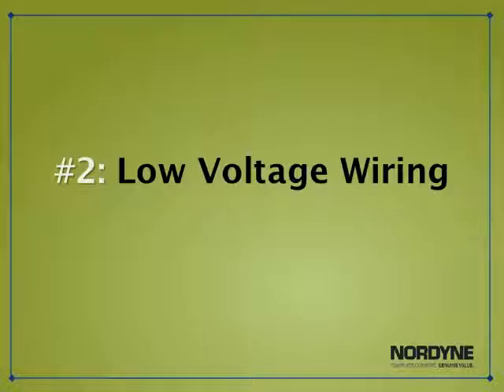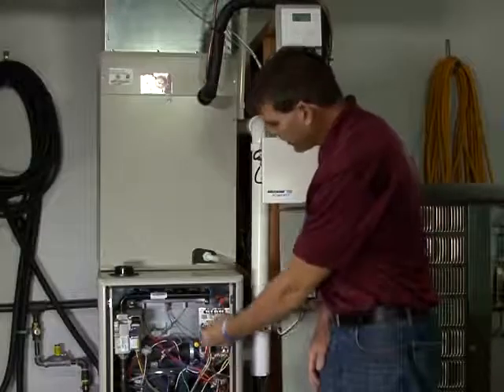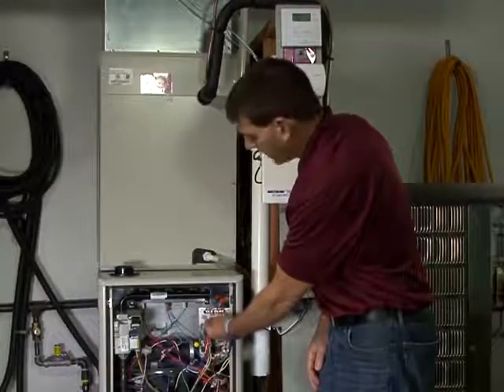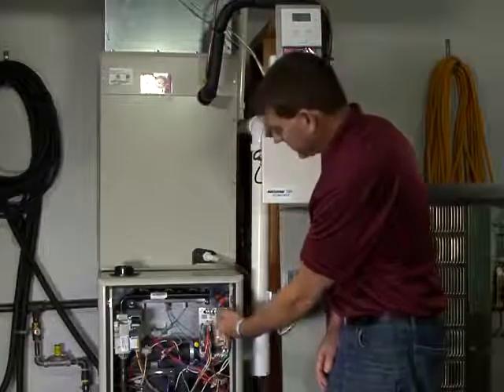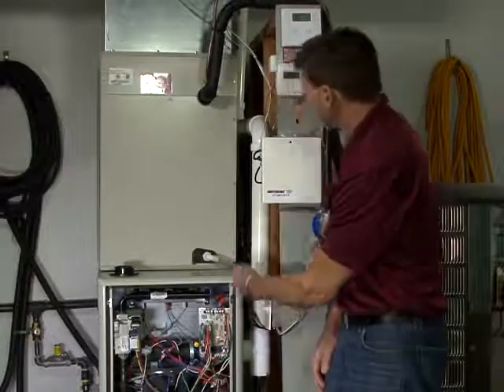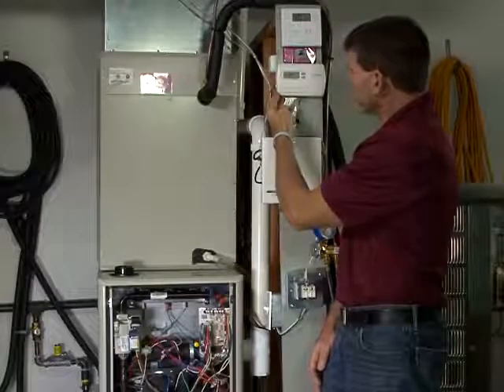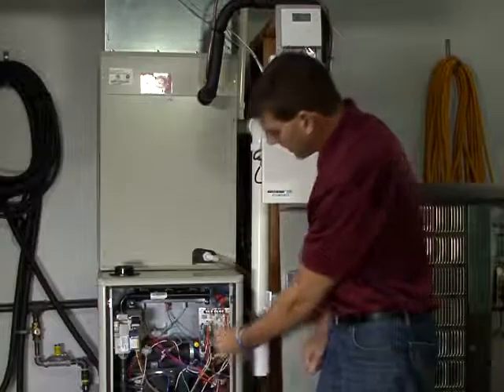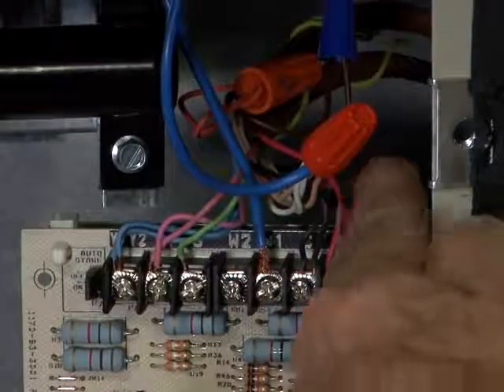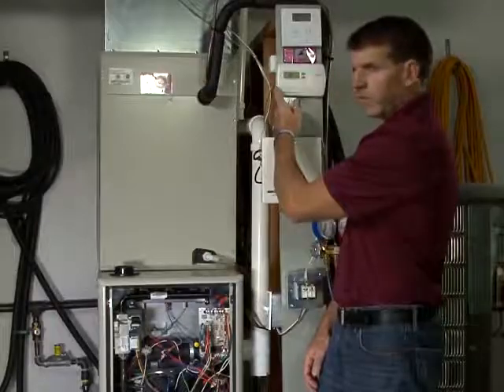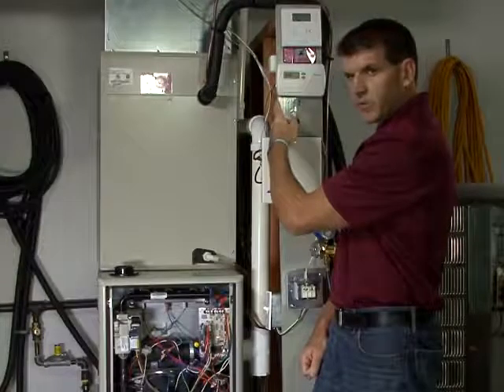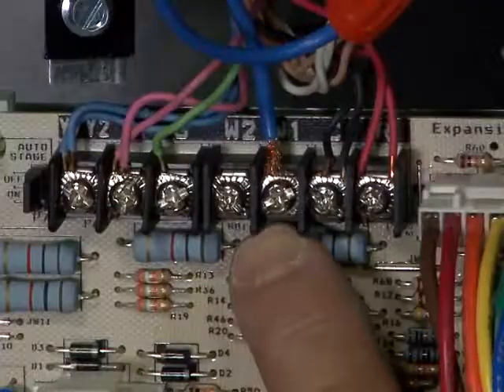Our next topic we're going to cover is a low voltage wiring circuit. Our low voltage wiring is what connects our thermostat to our interface control board. We also refer to this as our control wiring. Our control wiring connects at our interface control board on the terminal strip. It then runs through the thermostat wiring and connects to the thermostat. Our control board sends 24 volts from the R terminal on the control board to the R terminal on your thermostat. Your thermostat then, on a call for heat, will send 24 volts back to the furnace to the W terminal to initiate a call for heat.